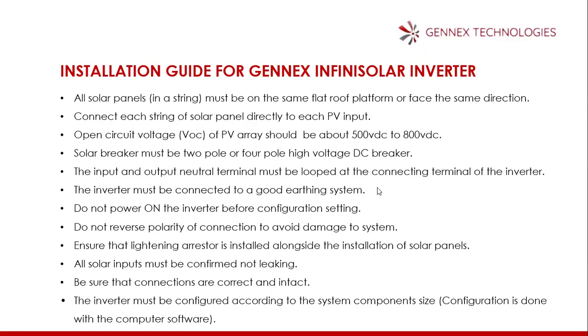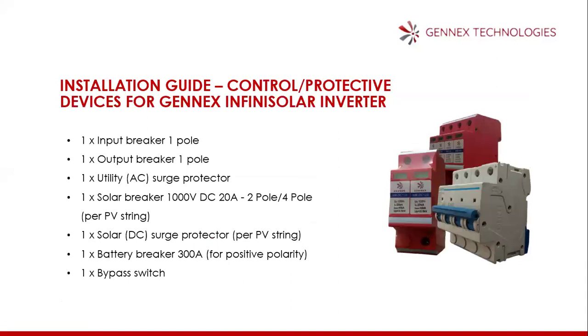Installation guide, control and protective devices for Gennex InfiniSolar inverter. You need to have at least 1 unit of input breaker, a single pole for 1 inverter. 1 unit of output breaker.